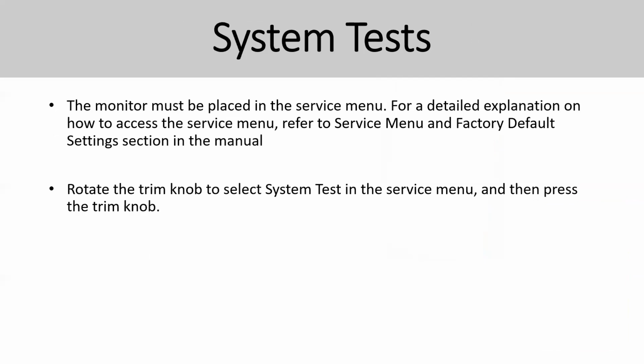System test is basically a self-test when you power on the particular device. It's going to check whether the system is working properly or not. At the same time, a system test can be done by using the service menu, but you need to have certain service access. So you need to have some password, depending on the brand and model. Sometimes you can enter this particular setup and check the system test.